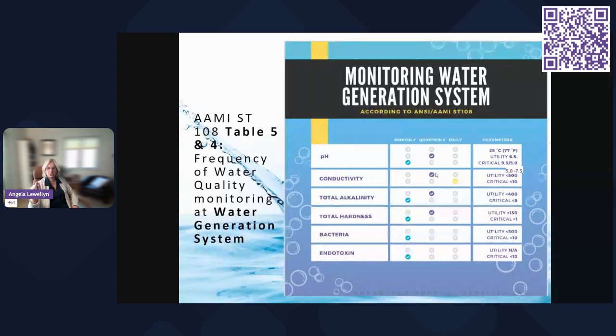pH should be measured at 25 degrees Celsius, 77 Fahrenheit. Utility water should be 6.5 to 9.5, tested quarterly. Critical water starts at 5.0, tested monthly. You can see the checkpoint and check mark and line that up. Again, if you have any questions about this chart, please don't hesitate to reach out and I'll walk you through it.